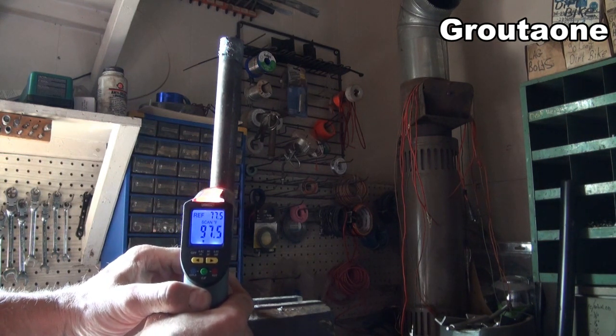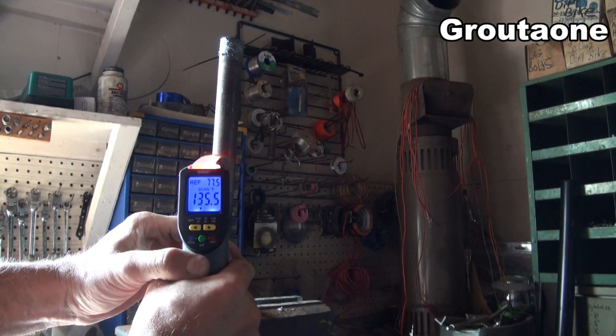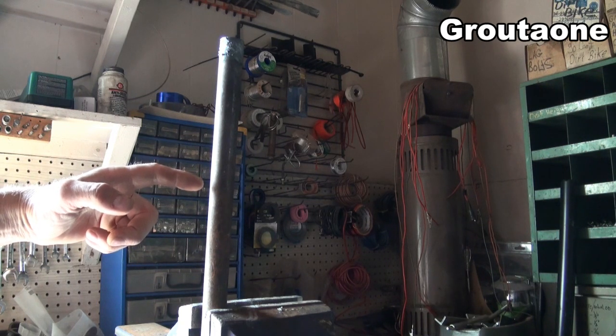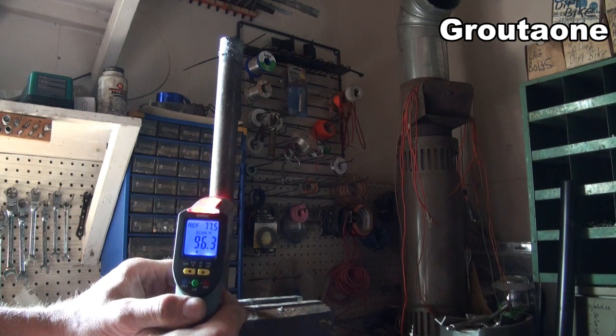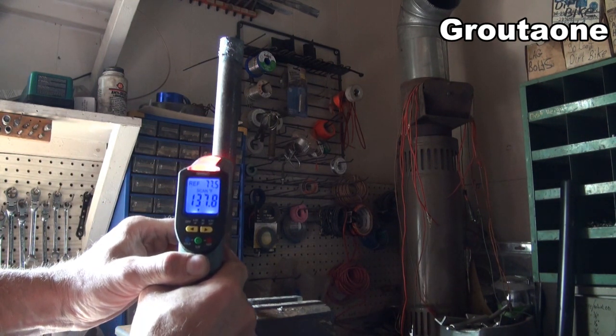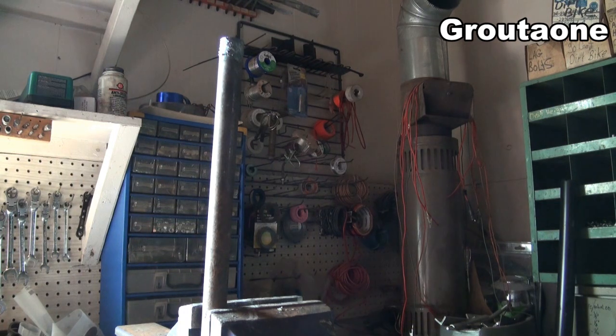So 135 degrees right here, and I'm really sure there was never any flame that actually flickered down to there — the flame maybe came down to this far. So I think there's been a lot of cement pads improperly poured with floor heat because of that misinformation. 150 degrees, 147 right here. So if you pour pads thinking heat only goes up — well, in a solid state it actually goes equally in all directions. Anyway, just kind of putting that to rest.